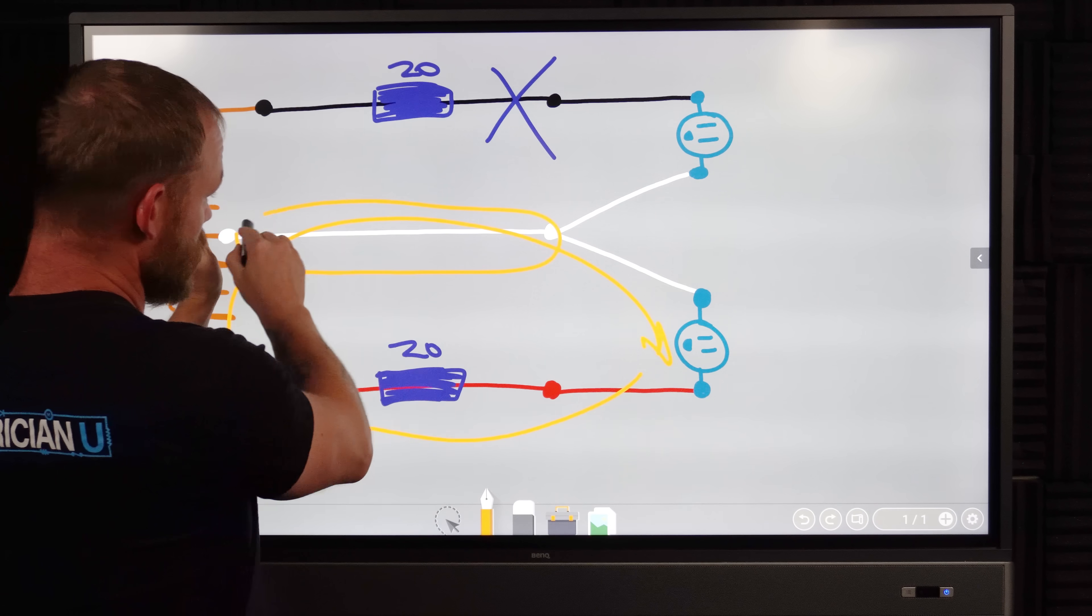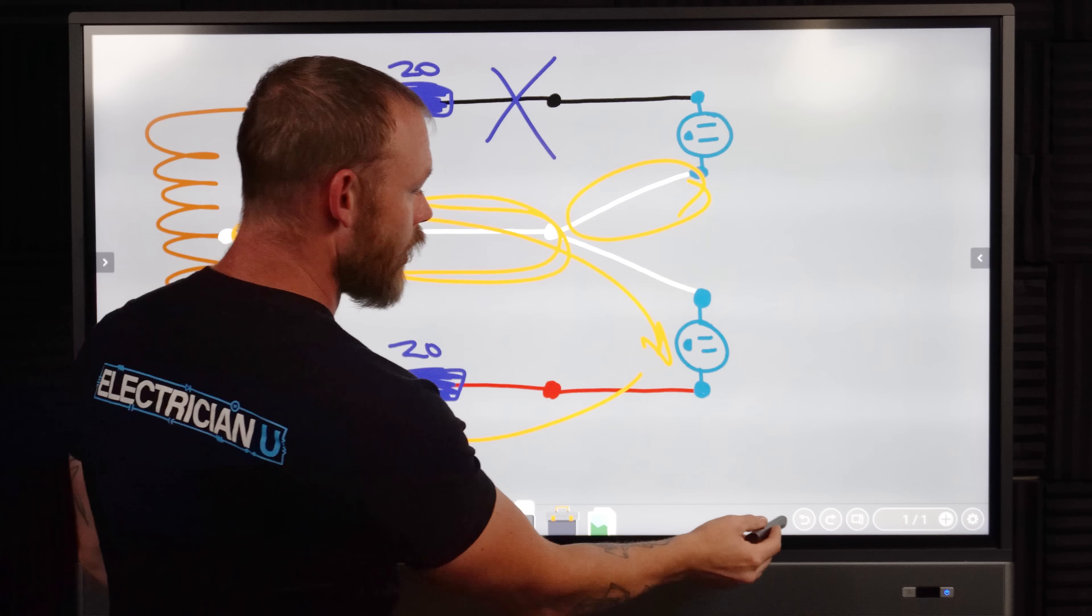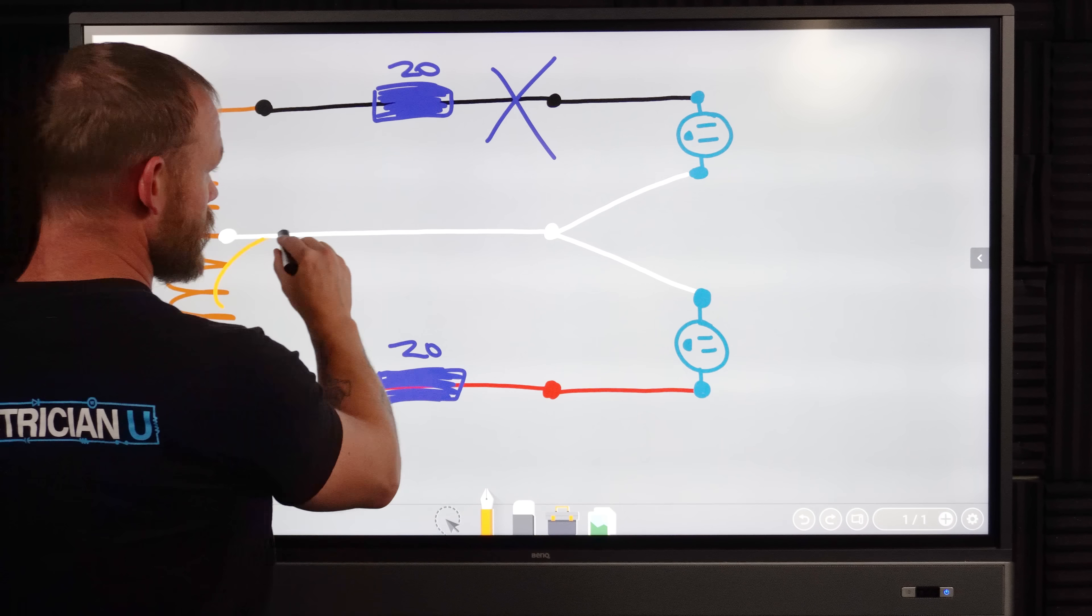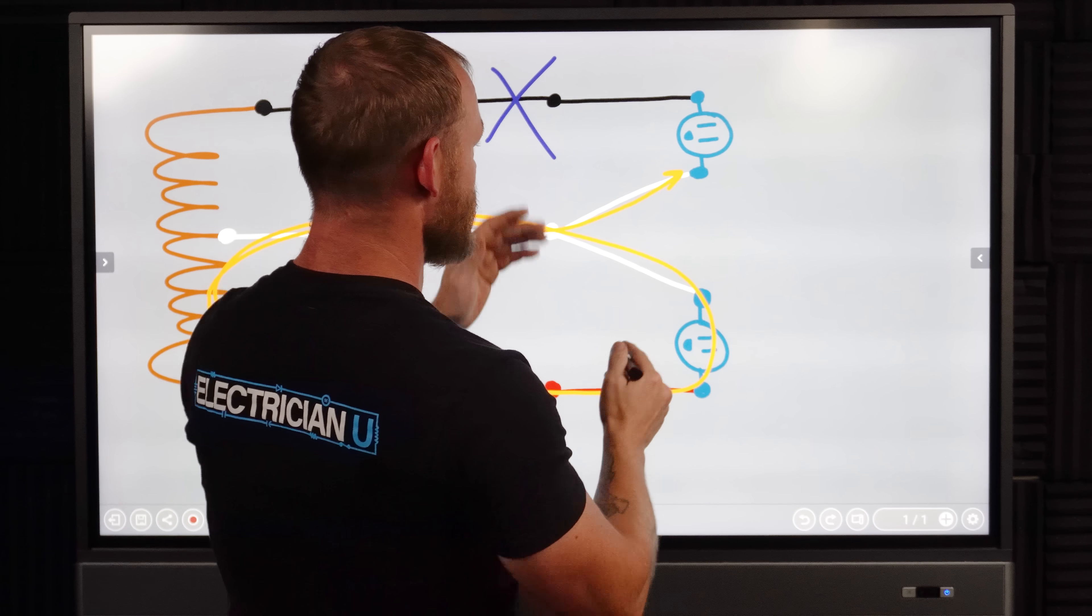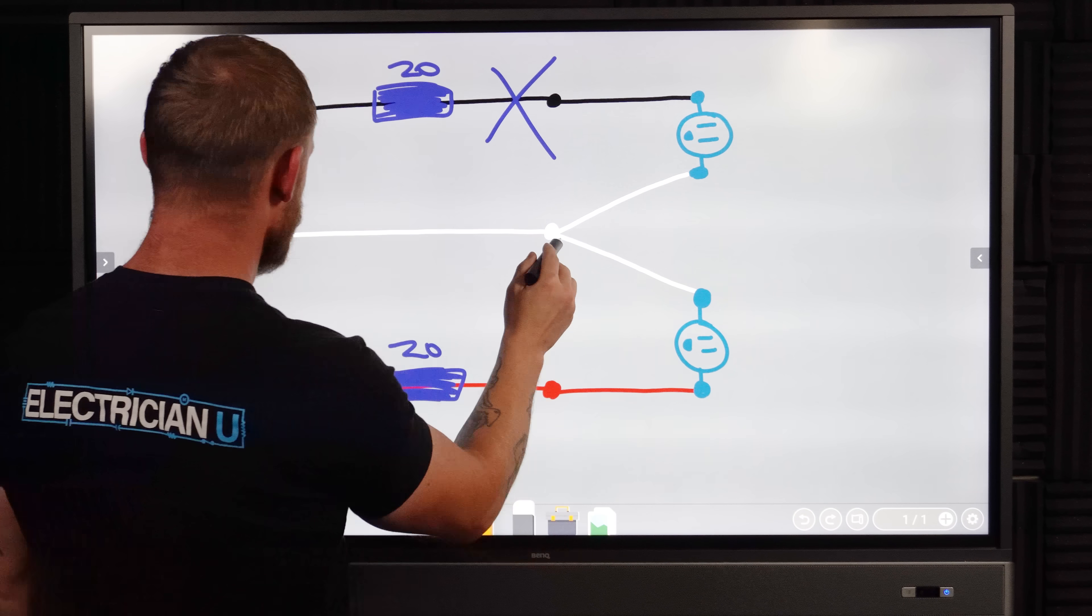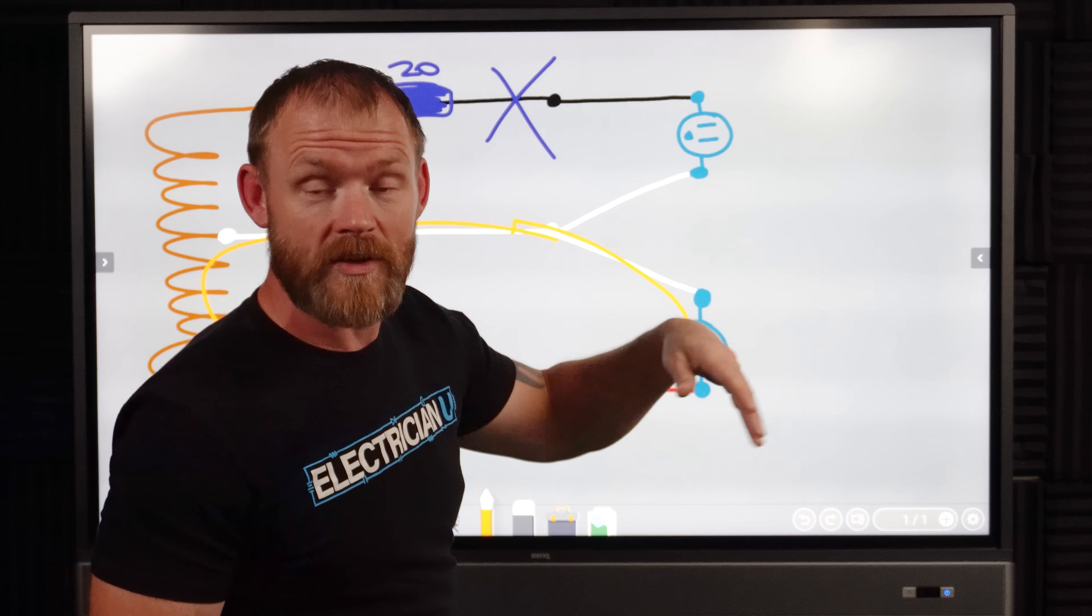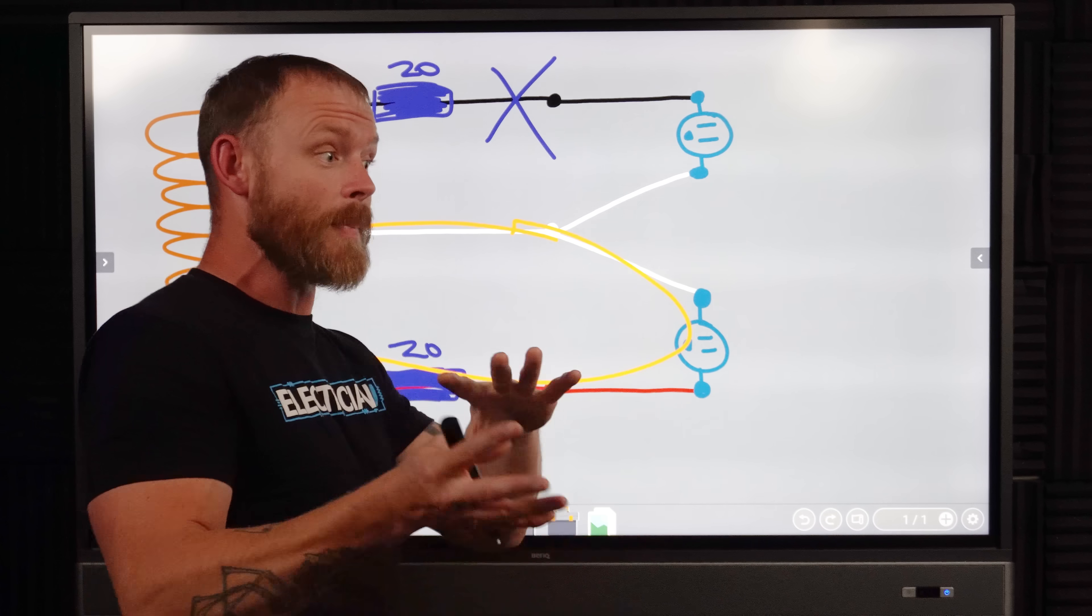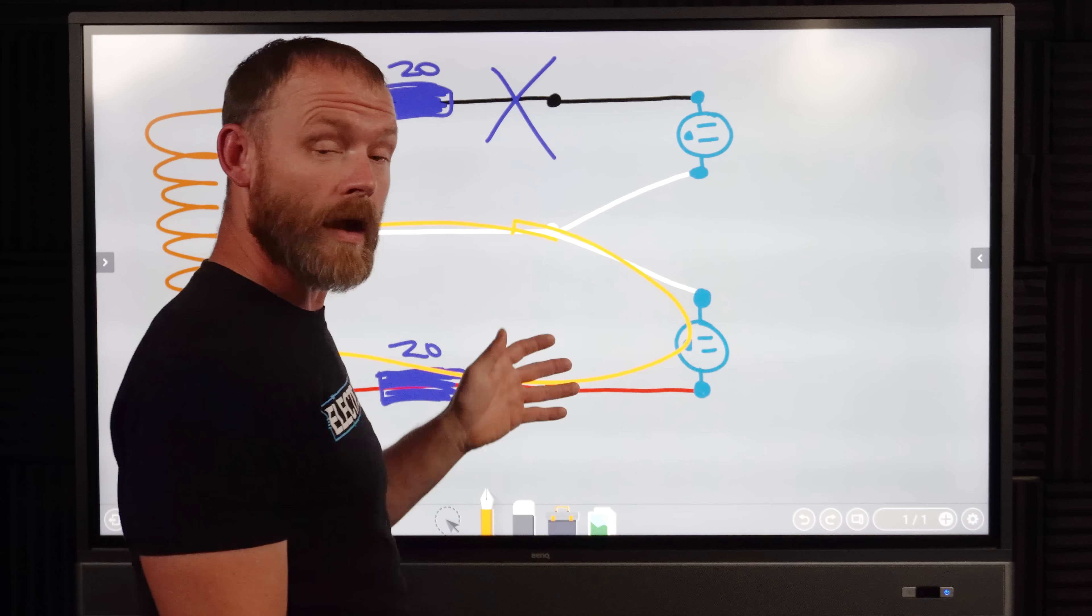What we don't realize is that right here, this circuit is still a complete circuit. So you still have potential all the way through this whole circuit. So this part of this neutral can still have current on it. This part won't absolutely, because we don't have a complete circuit anywhere. And the current always travels in a path of a loop. So current is not going to travel in a place if it's got a loop here, it'll travel in that loop, but it's not just going to like magically go out here and sit here on a wire that's not connected. If there was another completed loop, like absolutely it would, but it doesn't have a complete loop that way. So there's not going to be any current right there. There's only current in this portion of the circuit, but Mr. Helper going in, not realizing being like, oh, I just shut the black circuit off and didn't realize it's a shared neutral circuit. And none of the journeyman had actually told him like, Hey dude, there's potential for that neutral to be able to bite you depending on where you're actually taking it apart and messing with it. You could still have current flowing on this one and still get shocked by a neutral. So be really, really careful on shared neutral circuits.